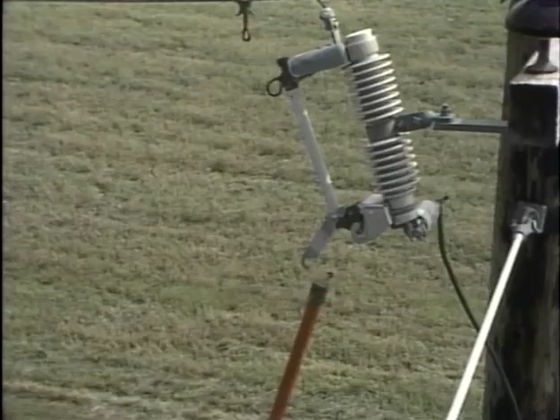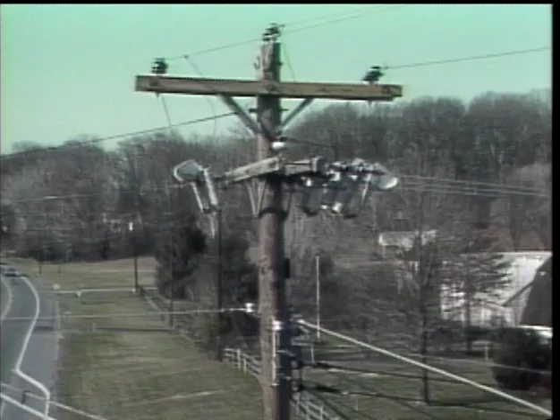At the hinge in the switching arm, the fuse link is connected to a latch. To de-energize and isolate a circuit under load, a hot stick can be used to push up on the latch. Pushing up on the latch breaks the fuse and causes the switching arm to spring open. Because the circuit is broken by the fuse, any arc is contained and extinguished within the fuse tube. Other load break switches can have arc breaking devices attached to them. These devices can help distinguish a load break switch from a no-load switch.